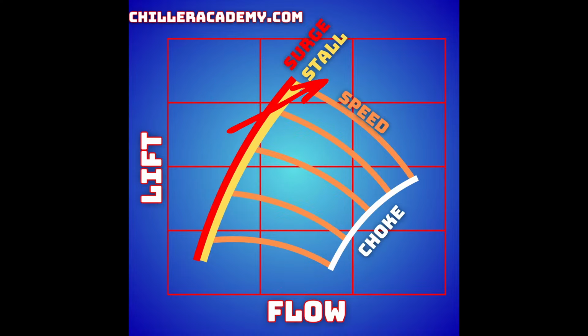Okay, so surge and stall are over here on this end of the system where we're running lower flows but high lift. Choke is on the opposite end where we've got low lift with high flow. And we want to stay in this middle zone in between here. Now, let's just assume you've got low flow, so we've got a low load, but we've also got low lift.